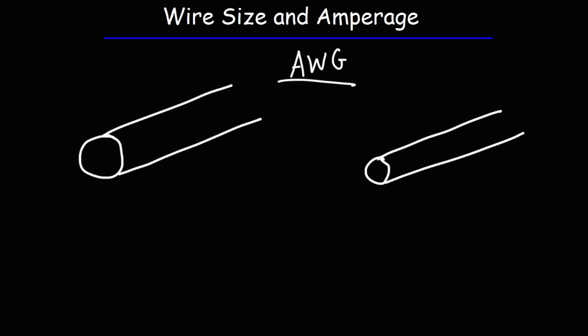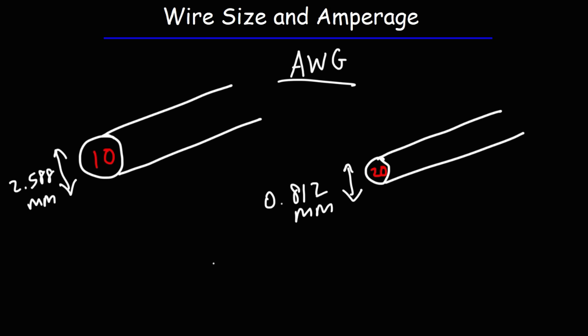The picture on the left represents a wire gauge of 10, and the one on the right represents a wire gauge of 20. What you need to understand is that the higher number corresponds to a smaller wire. A wire gauge of 10 has a diameter of about 2.588 millimeters, whereas a wire with a gauge of 20 has a diameter of 0.812 millimeters. As the wire gauge increases in number, the diameter decreases — so these two are inversely related.